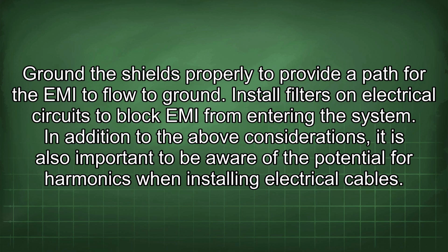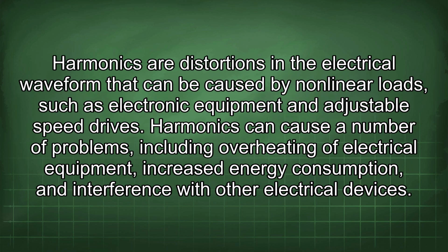In addition to the above considerations, it is also important to be aware of the potential for harmonics when installing electrical cables. Harmonics are distortions in the electrical waveform that can be caused by nonlinear loads, such as electronic equipment and adjustable speed drives. Harmonics can cause a number of problems, including overheating of electrical equipment, increased energy consumption, and interference with other electrical devices.